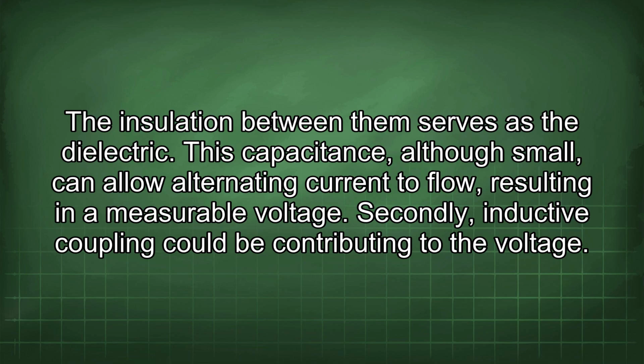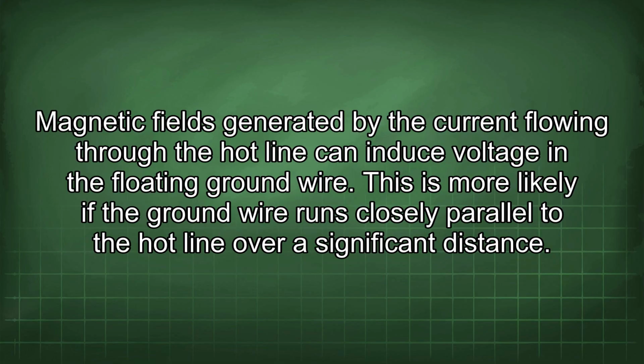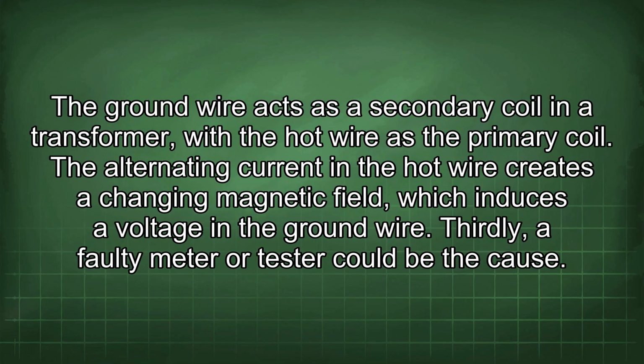Secondly, inductive coupling could be contributing to the voltage. Magnetic fields generated by the current flowing through the hot line can induce voltage in the floating ground wire. This is more likely if the ground wire runs closely parallel to the hot line over a significant distance. The ground wire acts as a secondary coil in a transformer, with the hot wire as the primary coil. The alternating current in the hot wire creates a changing magnetic field, which induces a voltage in the ground wire.